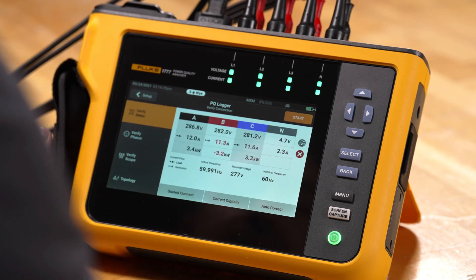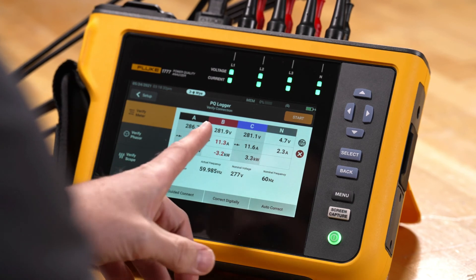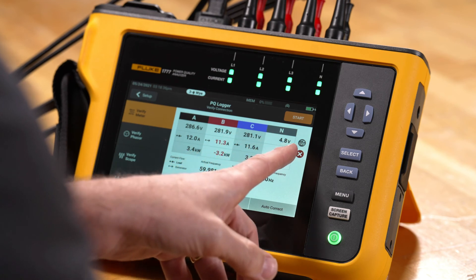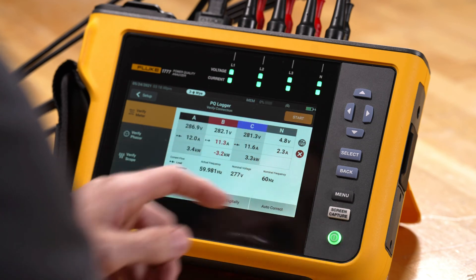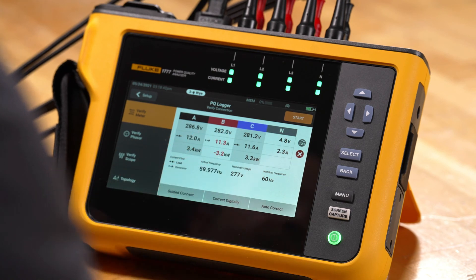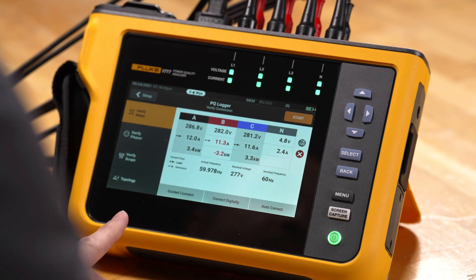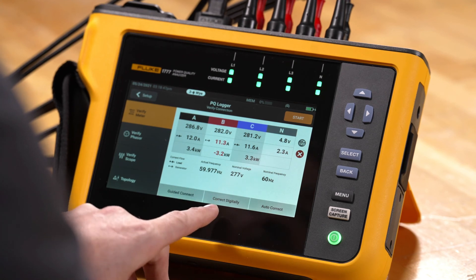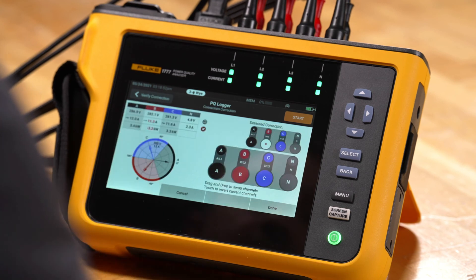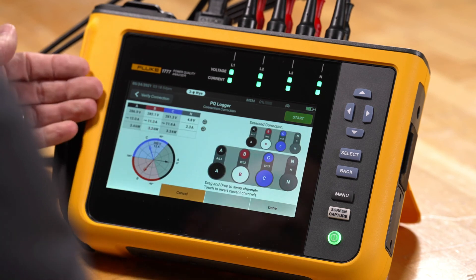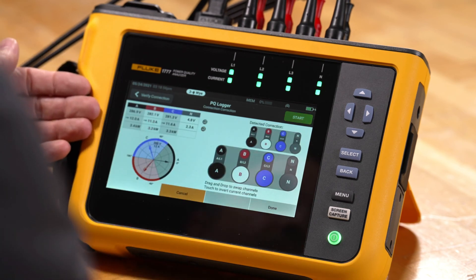Going back to verify meter, we can see red indicators for the B phase — there's an X indication and an orange start indicator. All of these tell us that there's a problem with the current configuration. We have the option to correct digitally or we can do autocorrect. By tapping autocorrect, the meter will go through and fix itself and correct the problems — no need to get back into the electrical panel, the fixes are all in place.